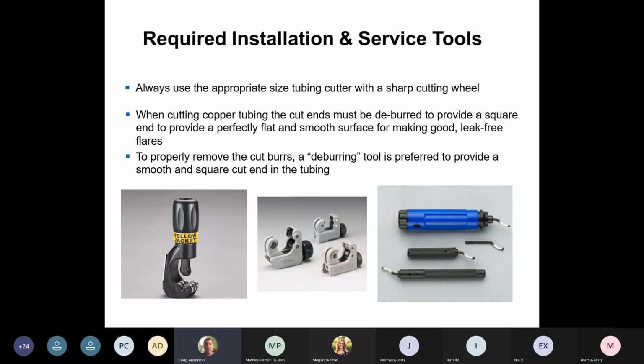If you don't deburr your copper on a standard air conditioner, you could get some noise with the freon going through the pipes. It's not flowing properly. We're getting some restriction. It does sometimes create some noise. So make sure you're deburring it and your cutters and all that are sharp and ready to go. You're not mushing the copper and stuff like that.